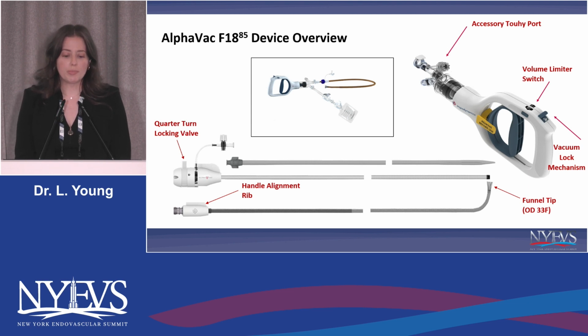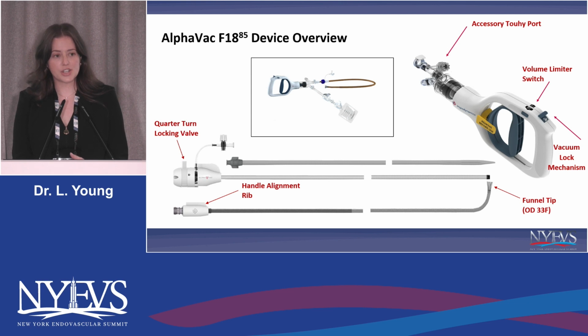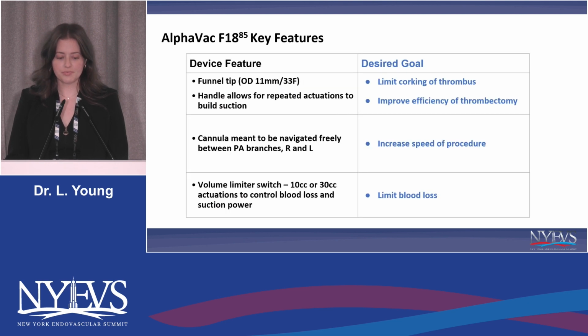So once you've built up some pressure, if there is, for example, something occluding the catheter or corked on the tip of the catheter, you can lock it if you do need to take the catheter out. And then there's also an accessory Touhy port. On the handle and also on the cannula itself, there's not a Luer lock or some other sort of injectable port to be able to do runs directly through the cannula or to take pressures. But you can insert up to an 8 French diagnostic catheter through the Touhy port and actually use that to take measurements and do runs if you want to.